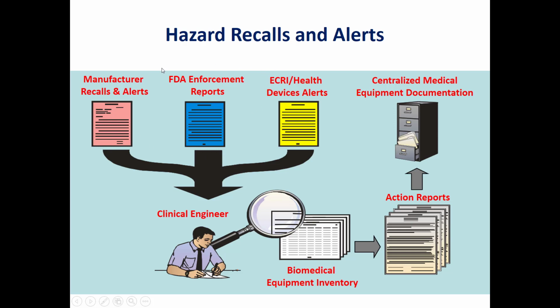So based on these reports, a notification will be sent to the clinical engineering, and a review of our database is made in order to decide if we need to take action or not. Then if a matching is found, an action will be taken. Then this action should be reported and documented.